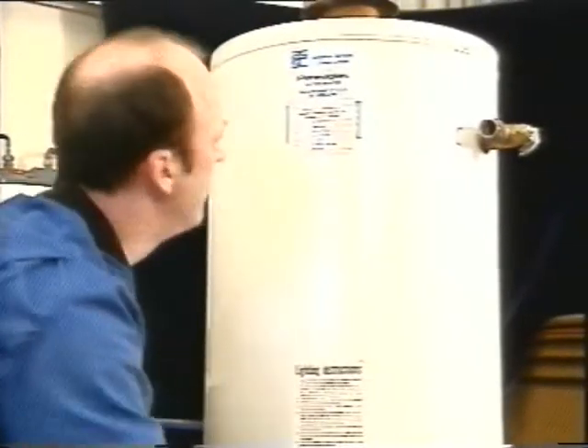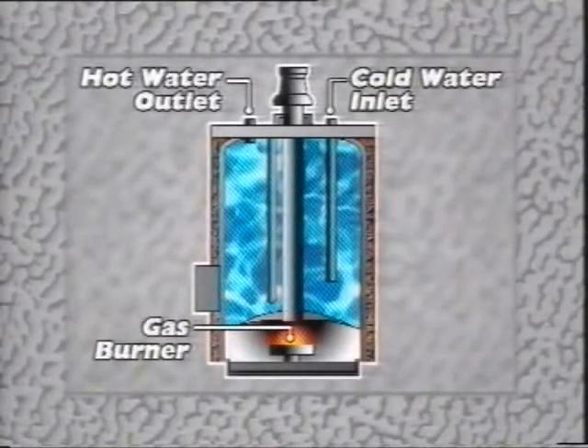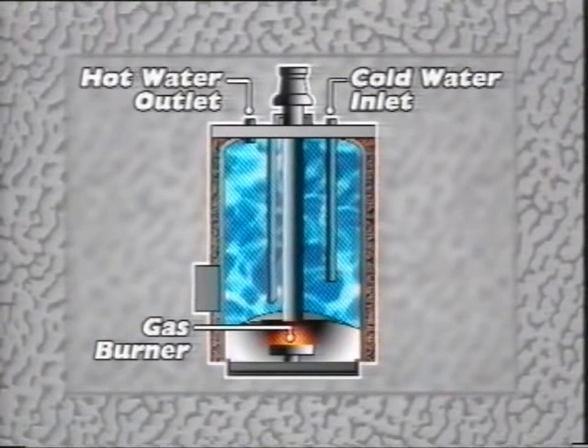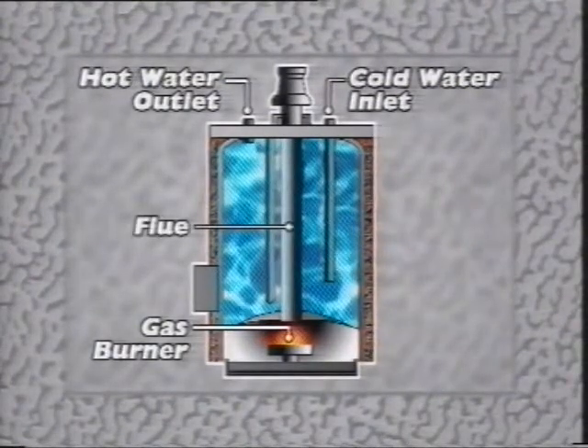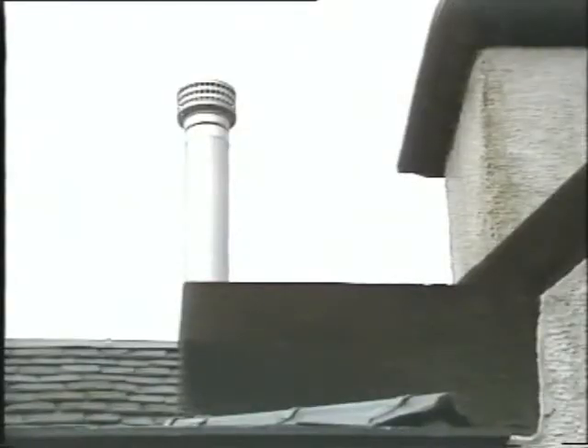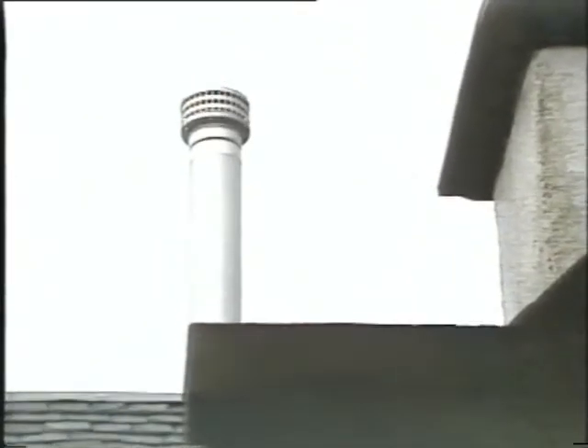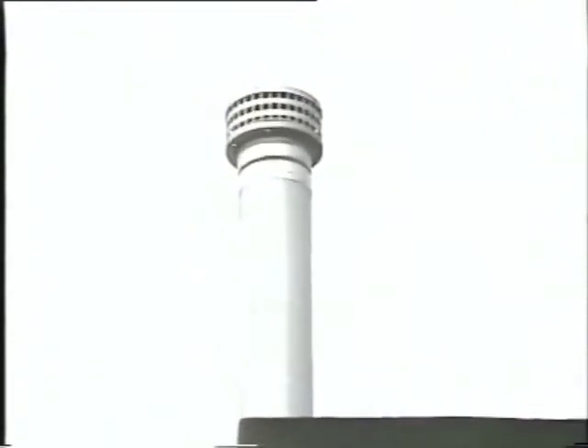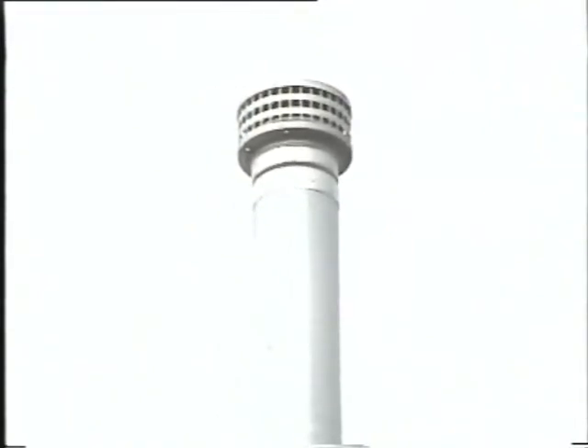It's not an instantaneous water heater, but basically a storage cylinder with a gas burner and a heat exchanger below it. Usually, its flue passes up through the center of the storage cylinder. The typical heat input for one of these is between 6.5 and 8 kilowatts. So if it's an open flue type, ventilation is very important. As with everything else, the way to make sure you're doing the right thing is to check the manufacturer's instructions and the BS regulations.